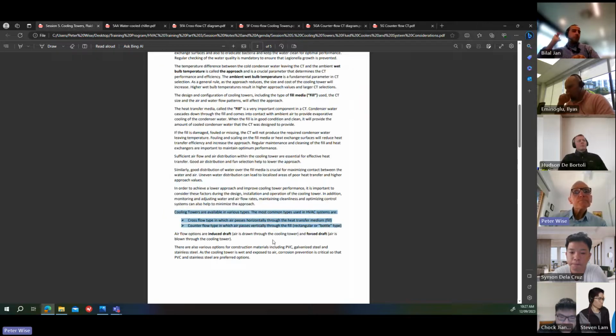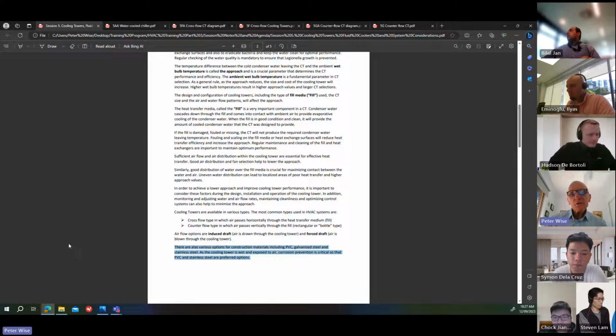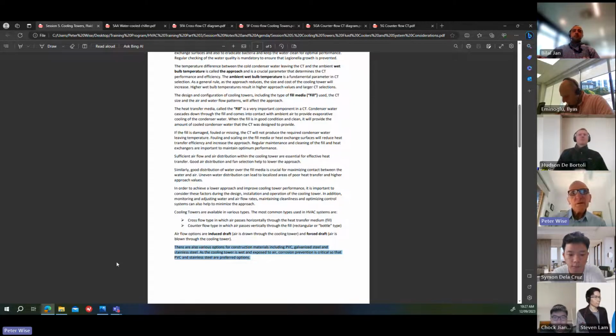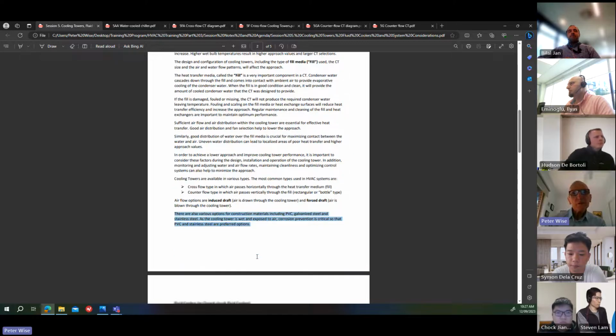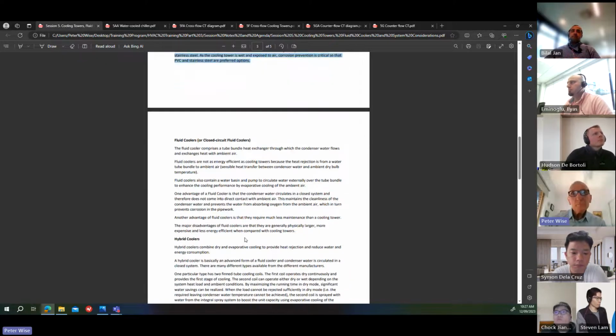So, in terms of materials for cooling towers, there's various options, including PVC, galvanized steel, and stainless steel. As the cooling tower is wet and exposed to air all the time, corrosion prevention is critical, so PVC and stainless steel are the preferred options. Some manufacturers do make galvanized steel cooling towers, but there is a risk that they're going to rust over time. So just be careful in selecting those. They will be cheaper, but they may not be the longest lasting.